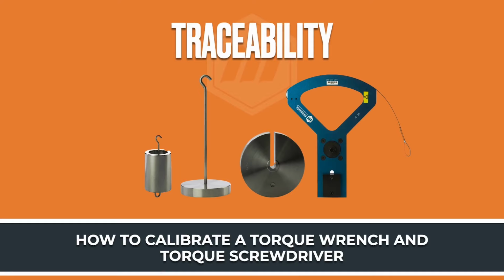Now, when we're talking about doing a calibration, we're actually doing a traceability chain, as it relates to how we can be sure that the output that we're getting is the correct torque output. And for the torque-related product, it all starts with wheels, segment arms, and weights. And this is how we calibrate a torque analyzer and torque sensor.